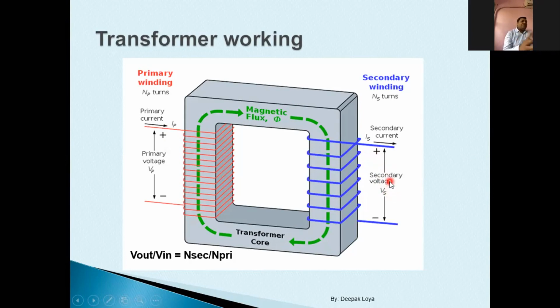Now, what will be the voltage ratio? If I am feeding 220 kV at the primary side, what voltage will I get at the secondary side? It depends on the ratio of your turns. What is the ratio of turns? How many turns I have in the primary and how many turns I have in the secondary. For example, if I want to step down 220 kV to 22 kV, that is 10 times, so my turns ratio has to be 10 times. That means if I put 100 turns for 220 kV, then in the secondary for 22 kV, I will have to add 10 turns.